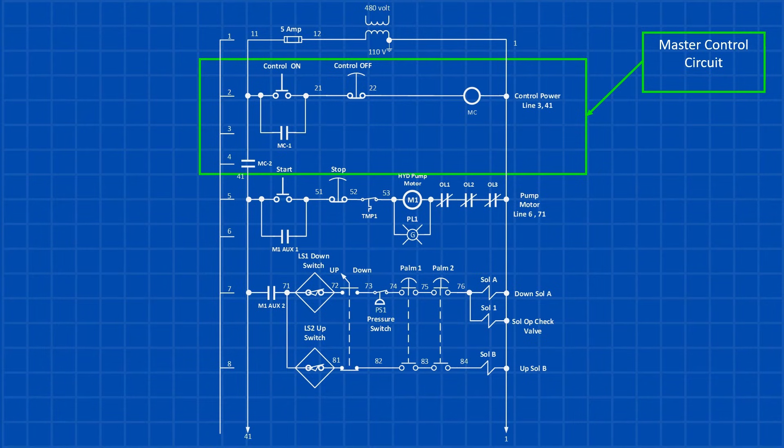In line two, pressing the control on push button energizes the master control relay. This action closes the auxiliary contact MC1, bypassing the momentary start push button and keeping the master circuit energized. Additionally, when the master control relay activates, the MC2 contact closes, allowing control power to flow to the rest of the circuit.